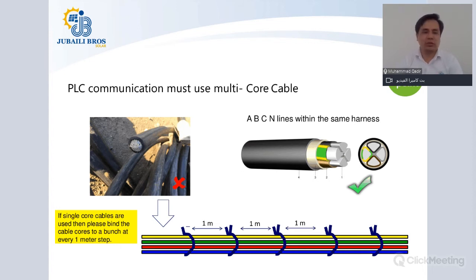PLC communication must use multi-core cable. Now, it is not a must. I would rather say it is recommended. Why? Because with the multi-core cable, you can go up to longer distance, and also with the single core, you normally need to tie the AC output cables at every meter length via cable tie, which is a very hectic process. So with the multi-core, you do not have to do such cable tying, and also you have the benefit of longer lengths between the inverter and the smart logger of up to 500 meters.